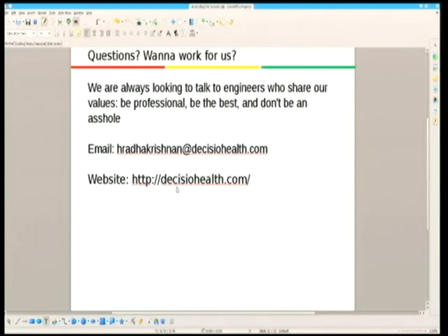Go ahead. Is code coverage part of the certification for the FDA? Yes, so when we ran our unit tests, we submitted the code coverage for the unit tests. When we wrote the documents, we said we would have 100% coverage. Obviously, you can't have 100% coverage, so we had to write a deviation saying why we didn't cover some parts of our code.